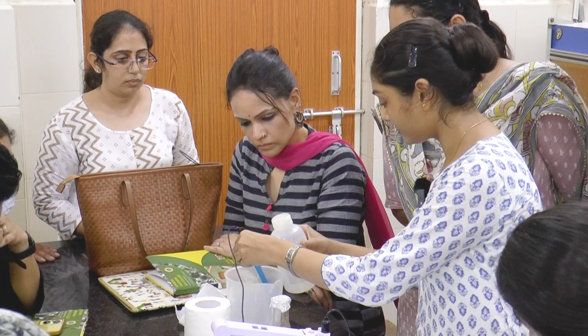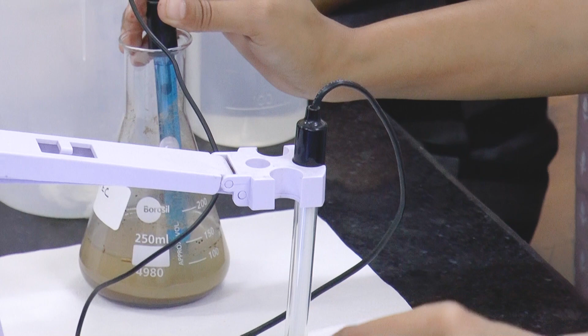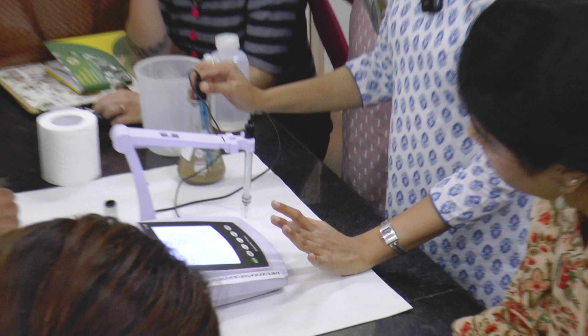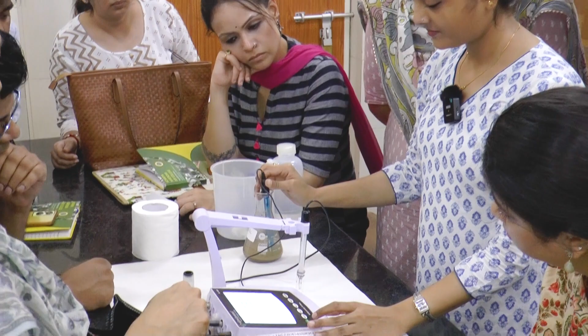This is the electrode for pH, and this is the electrode for electrical conductivity. First we measure the pH. Dip it in the solution, then we press the measure button here. It gives two indications: first it will show hold, then it will settle on stable. When it is stable, that will be our reading. It takes some time. 7.59. Then we can change the mode for electrical conductivity.